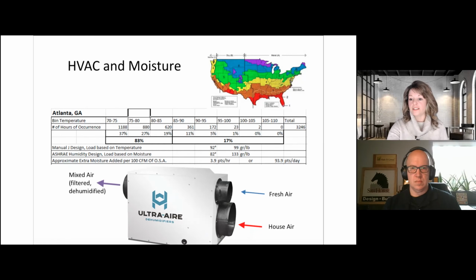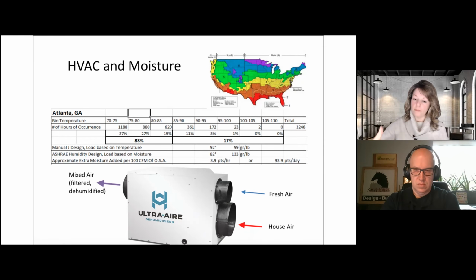And here, if you look at this Ultra-Aire unit, we can bring in outdoor air through the unit. We have a MERV 13 filter in this unit. So we're filtering the outdoor air with that MERV 13 filtration, very effective filtration. And then the house air is coming into the unit with a dedicated return, and that's getting filtered through a MERV 13, and then it's being delivered to the house.